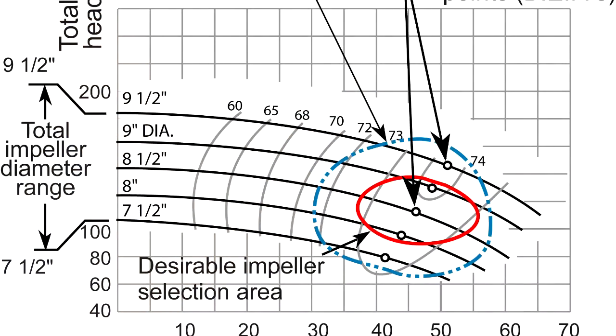For bigger industrial pumps we get curves that have a series of impeller sizes because you can order a pump with a smaller impeller or a bigger impeller depending on your operating conditions. But it's very similar to the curve I just showed you before and we still need to operate within that central region.